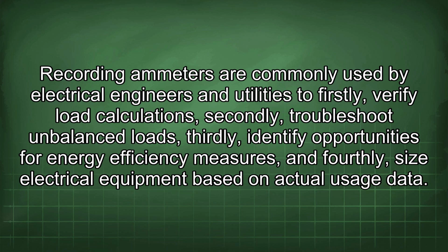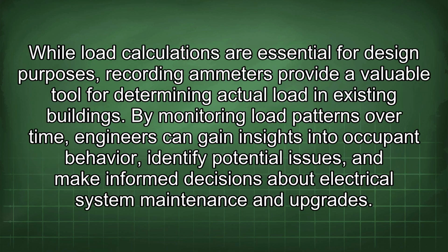imbalanced loads, thirdly, identify opportunities for energy efficiency measures, and fourthly, size electrical equipment based on actual usage data. While load calculations are essential for design purposes, recording ammeters provide a valuable tool for determining actual load in existing buildings. By monitoring load patterns over time, engineers can gain insights into occupant behavior, identify potential issues, and make informed decisions about electrical system maintenance and upgrades.